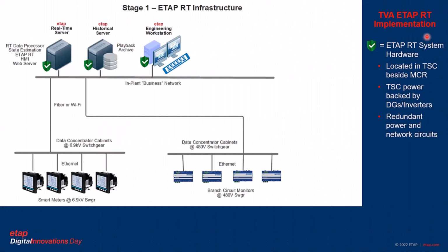So these are the things that will get installed in stage one. We can put in the branch circuit monitors and the smart meters, we can put them in the compartments, but just not connect them yet to the PTs and CTs. We can install the Ethernet, the data concentrator cabinets, any fiber, we can install the server, we can install the workstation. So these things can be done, as I said, during any normal work week.